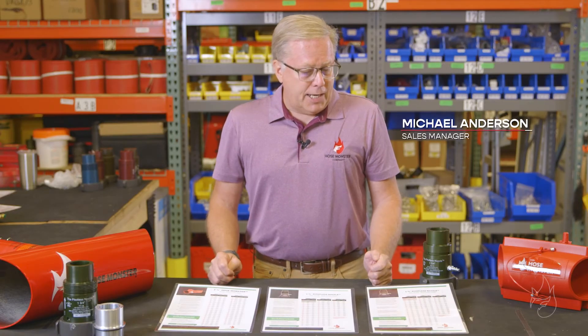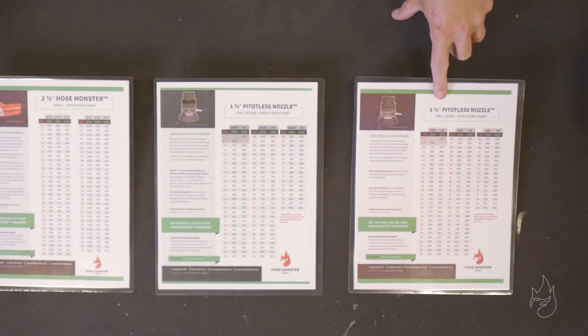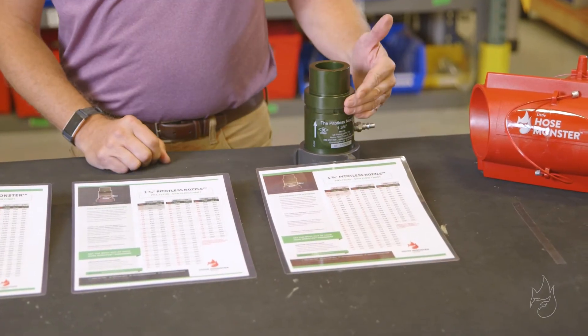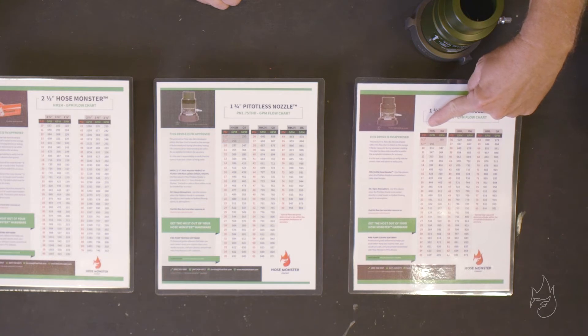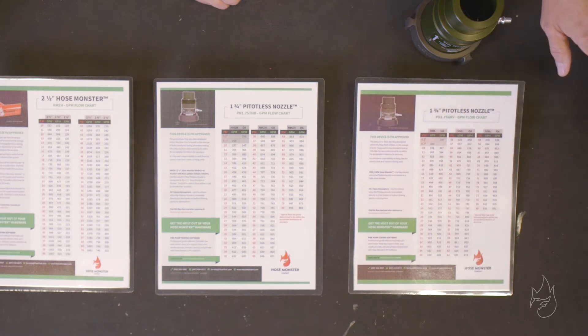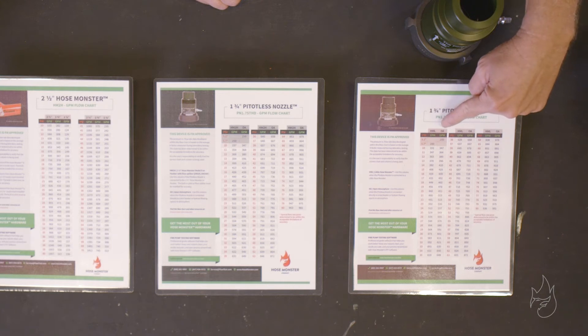Our instruction today is on how to read a flowchart and how to match that flowchart with the proper device. We're going to talk about the inch and three-quarter groove-style pitotless nozzle used with a little hose monster. On the flowchart, all readings would be taken and applied to this column when the pitotless nozzle is flowing through the little hose monster, or when it's hooked directly to a control valve, landing valve, or hydrant — we would use this column.